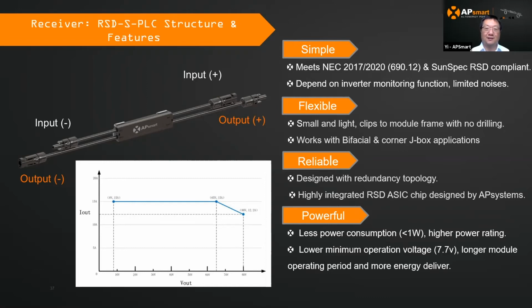This is a very important chart, because when you have a PV module vendor and want to know if they're feasible for the APSmart device, you can just compare with this chart. For instance, say you have a 40-volt VOC for your PV module and a 10 amp ISC level—that data point falls below these three data lines, which means under this area any module parameter will be feasible. Keep that in mind; it's a very easy way to select your PV module vendor.